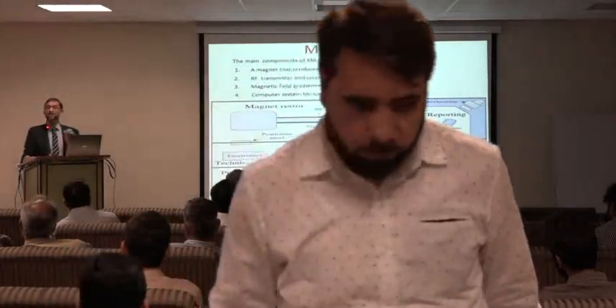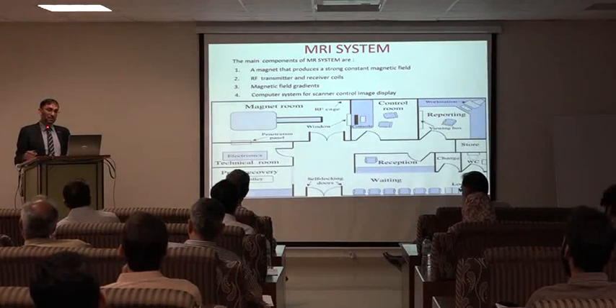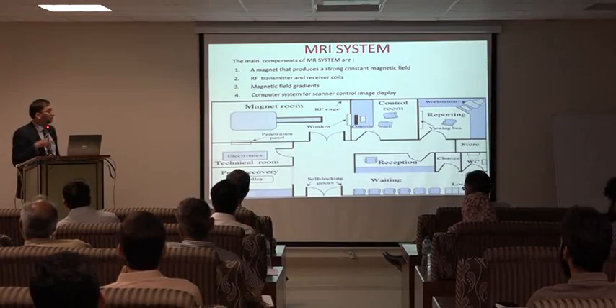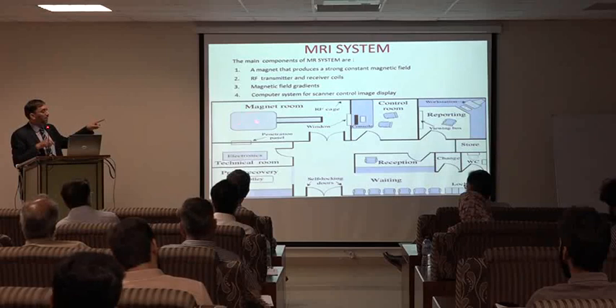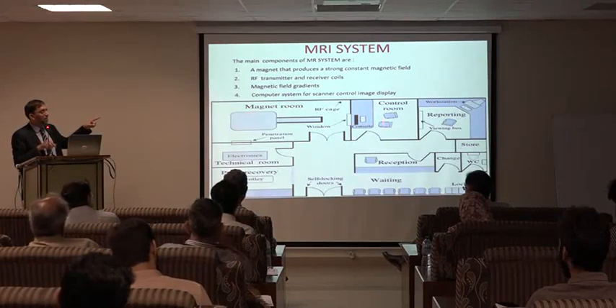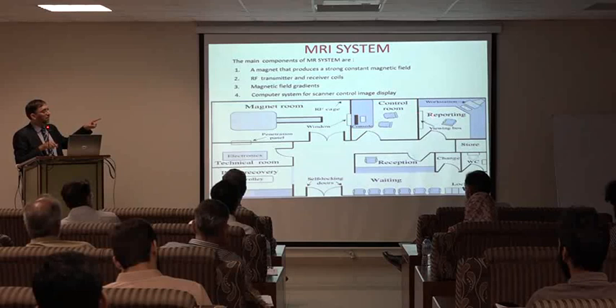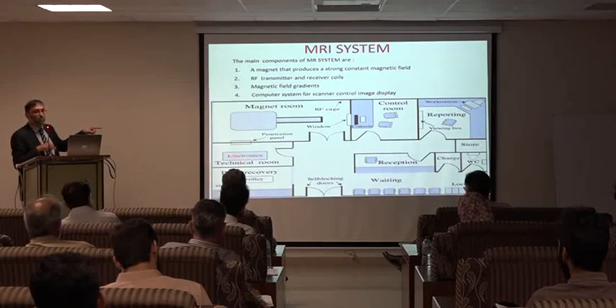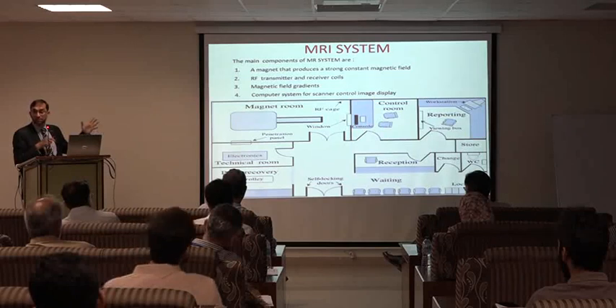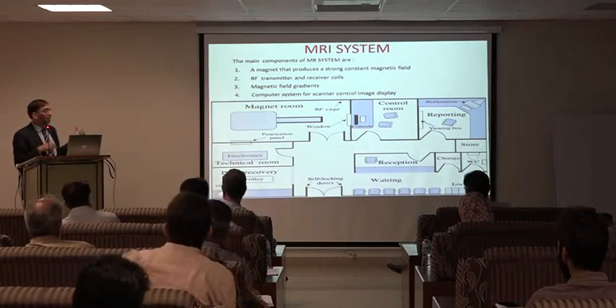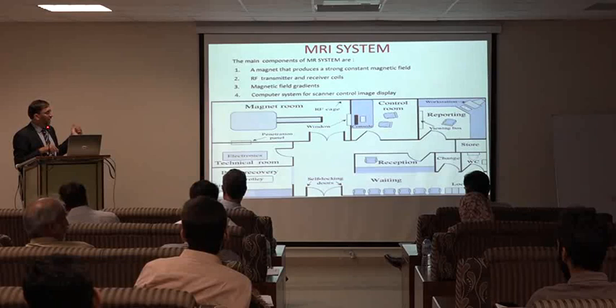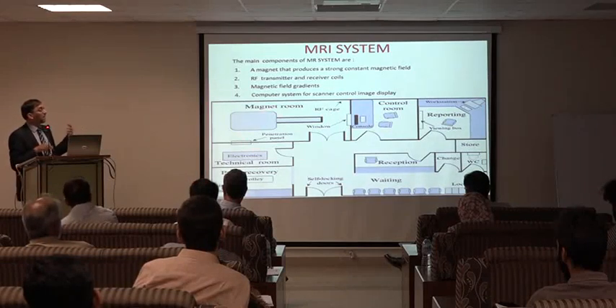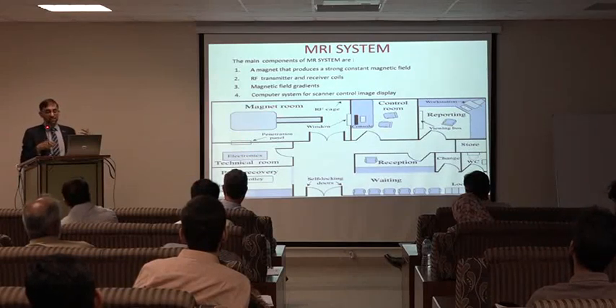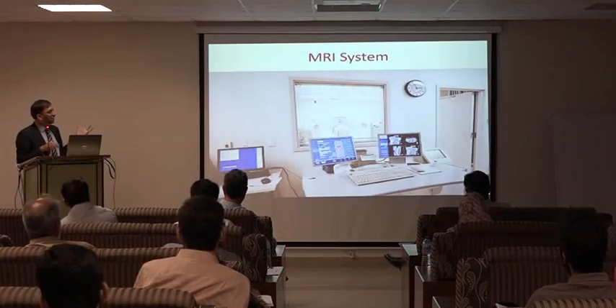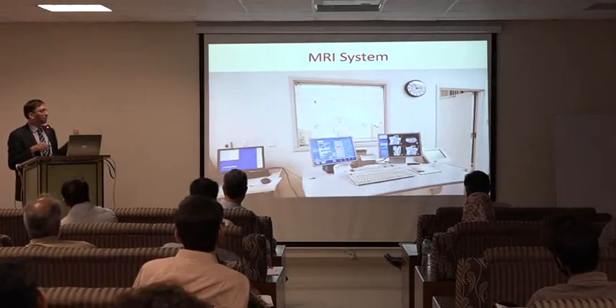I mean, it's a very strong magnetic field, right? So you can't even think about having any ferromagnetic objects inside this scanner room. So this is the main magnet room where the main magnet is, and there is a control room. This is where the people are sitting who are controlling the RF pulses. This is the reporting room, and this is the technical room where you have the PLC, programmable logic controller, big computer system which is controlling all the currents and everything about it. And then they are there. So I mean it has to be a big facility. MRI has to be a big facility. So this is, I mean, the people who have been to the scanner room, they'll know that this is where the magnet is, the main magnet is.